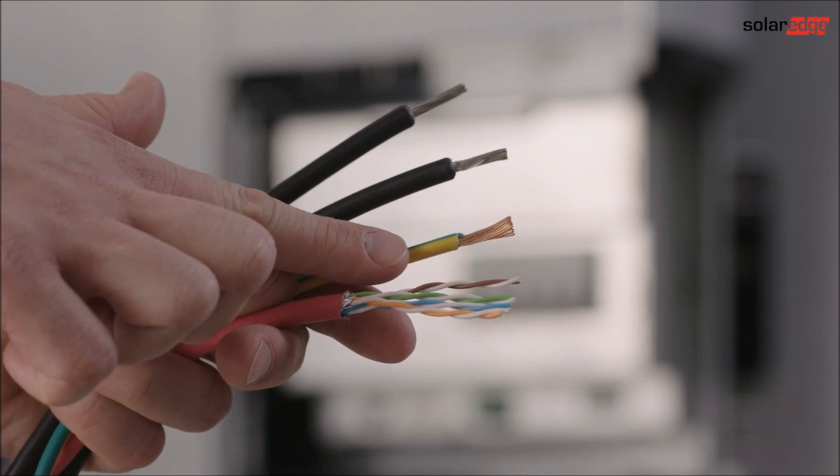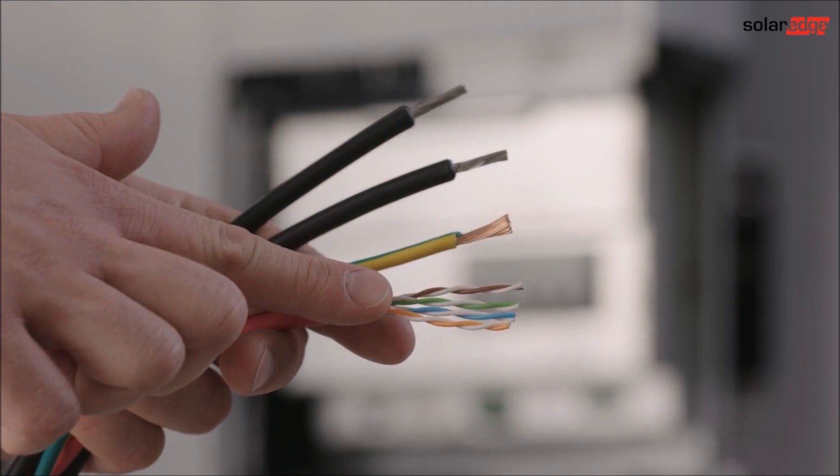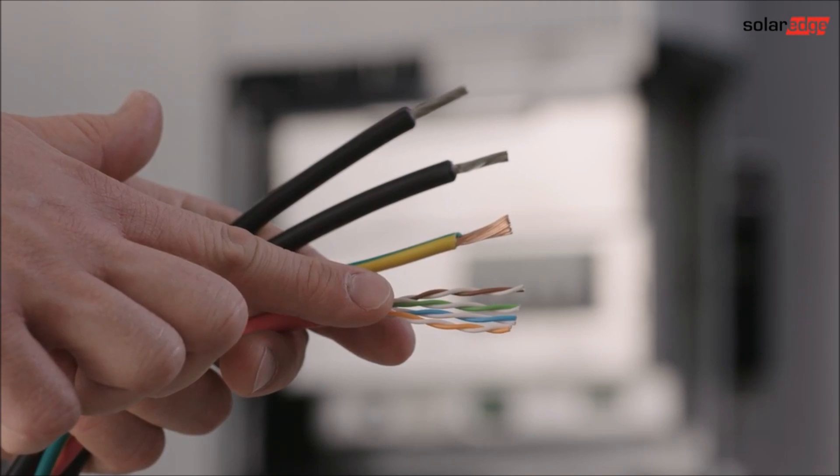A grounding cable according to battery manufacturer manual guidelines. Communication is done with a twisted pair cable. A 600 volt rated cat five or six cable is recommended.